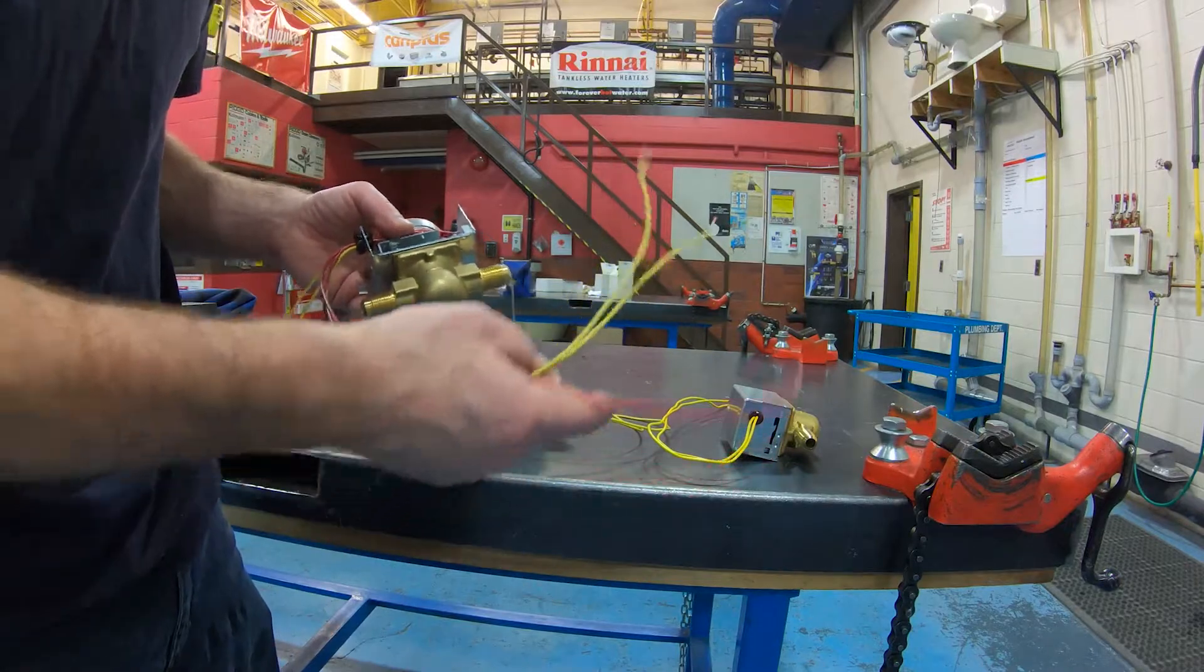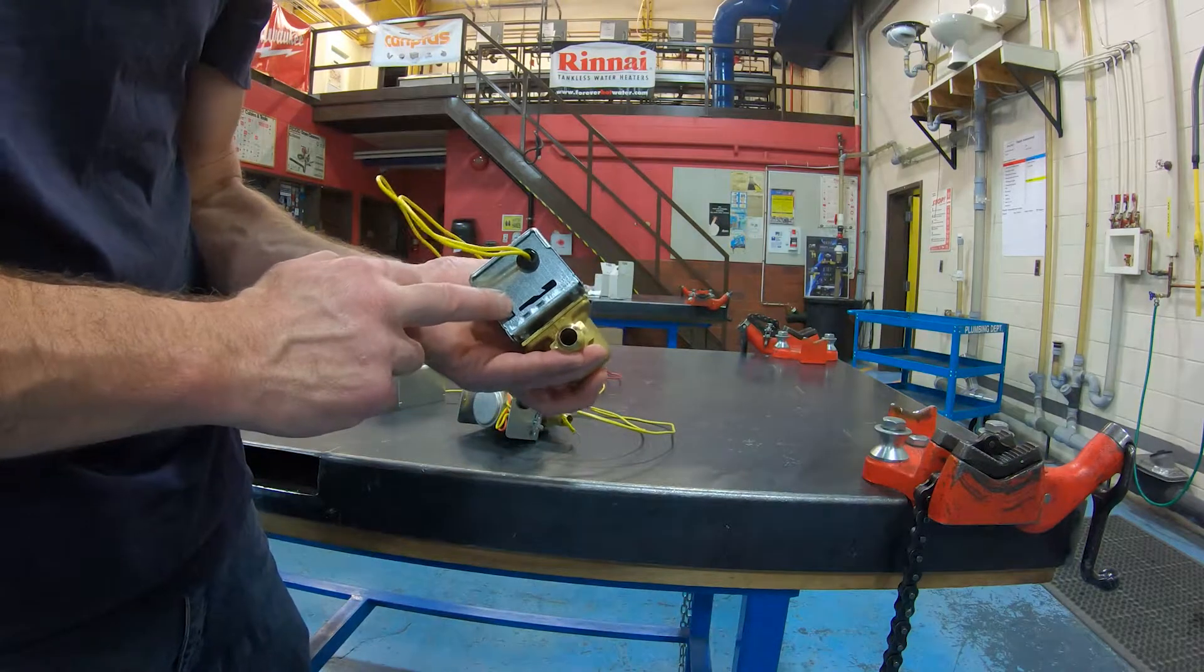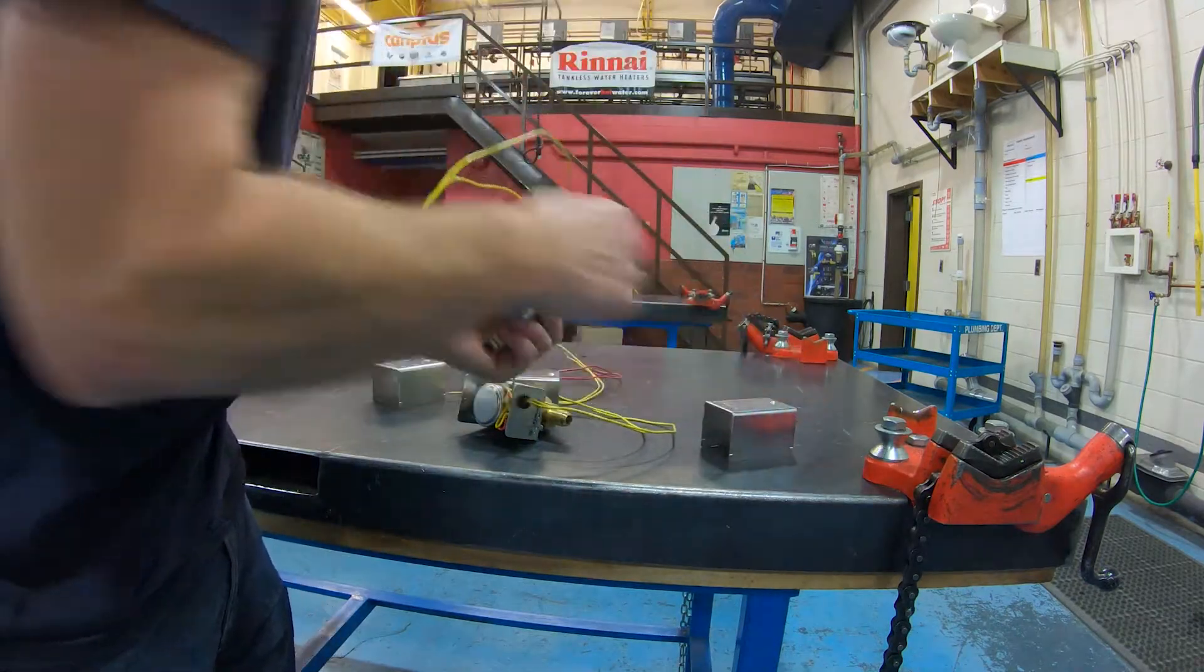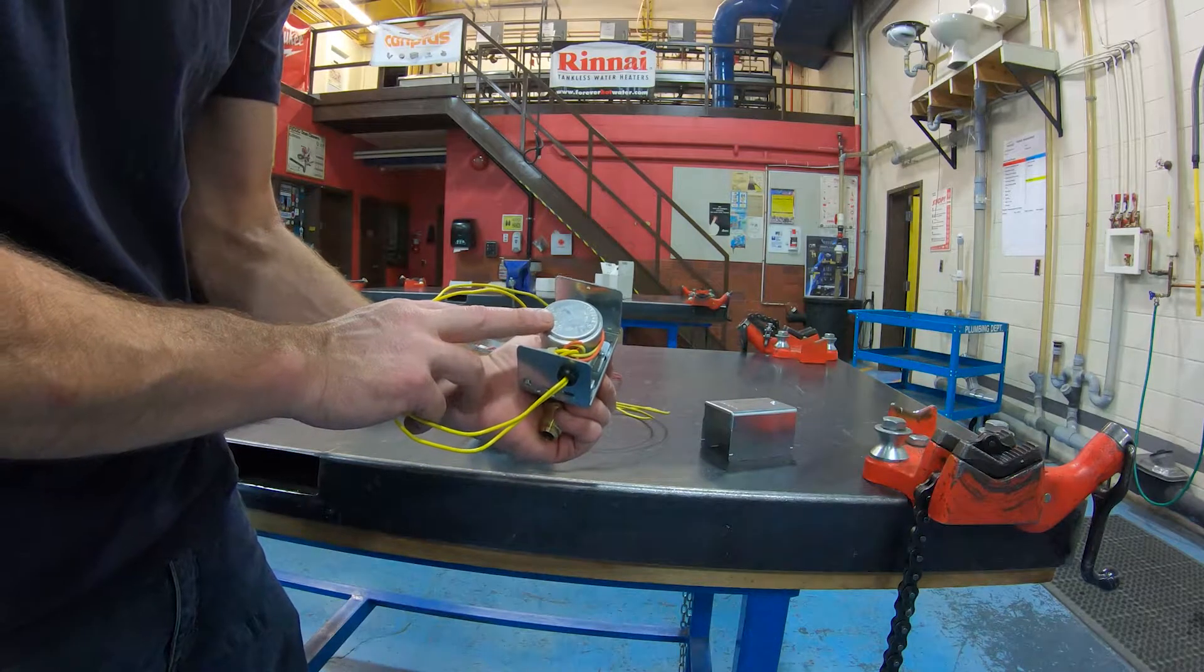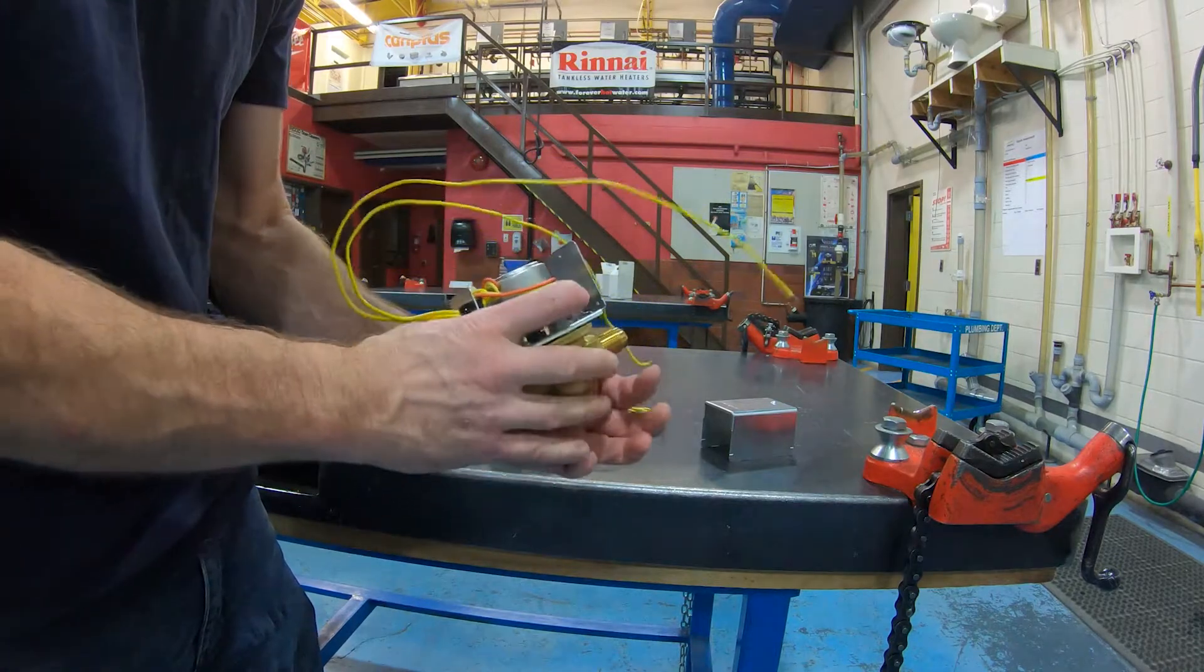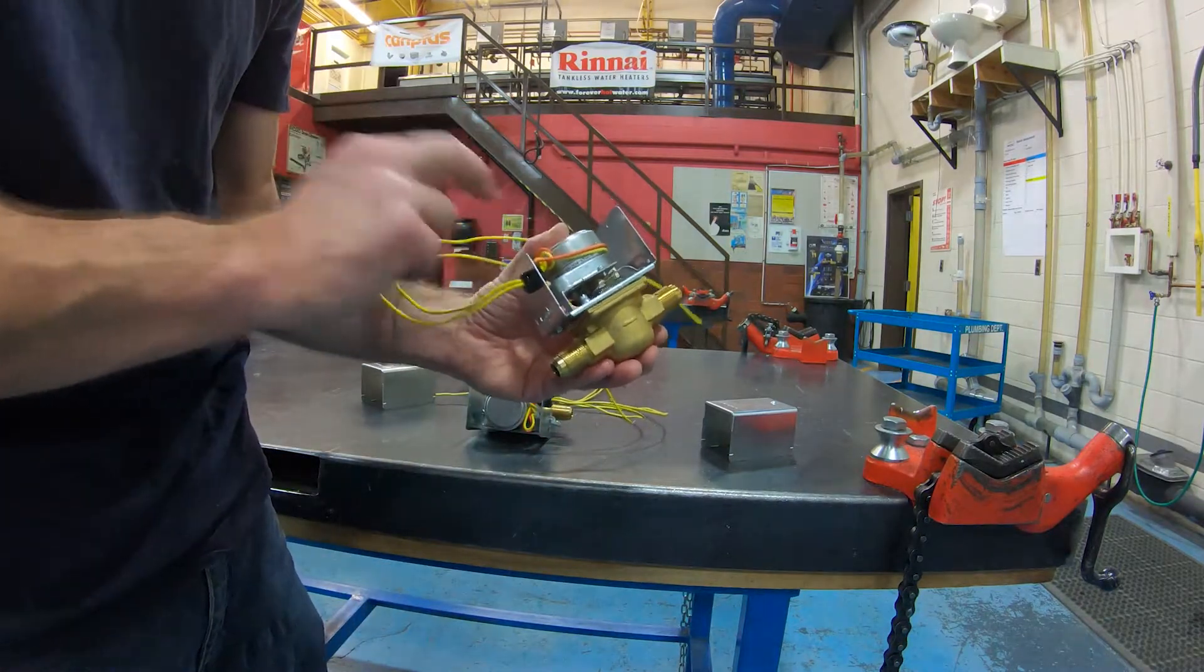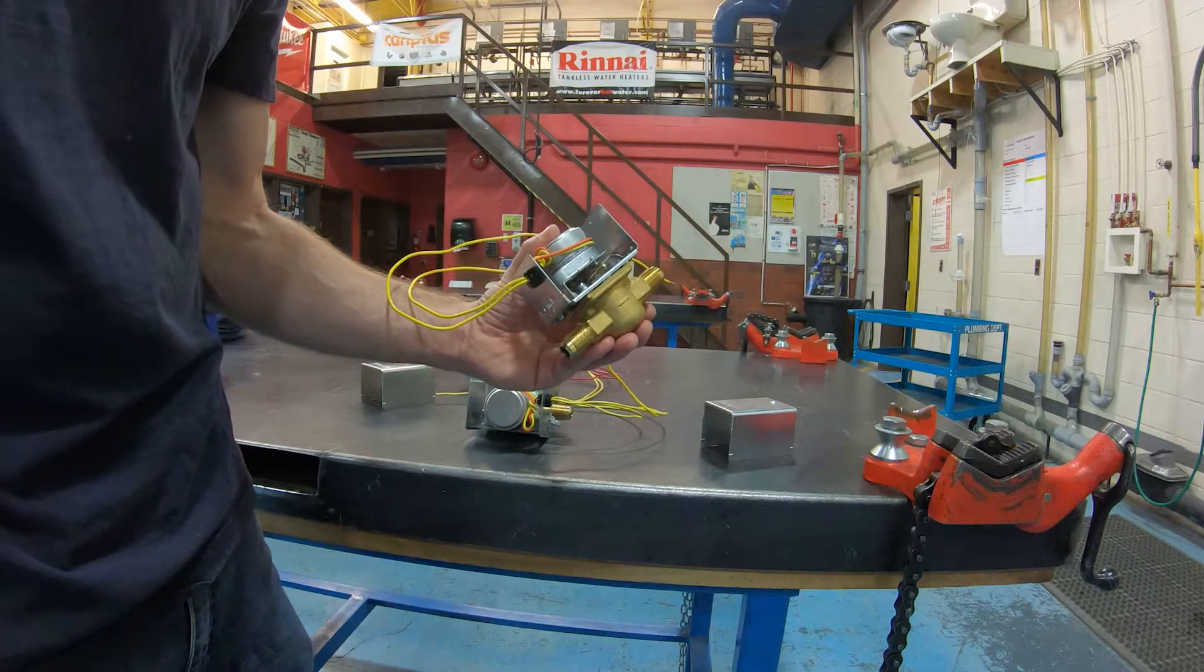Now the third type is a little bit weird. This type here has no manual tab. We call this a normally open zone valve. Still looks the same under the hood, we still have a zone valve motor, still a 24 volt actuator, still just two wires so there's no end switch on this. However, this particular type allows the water to flow through it until power is put onto the actuator. So no power means it keeps flowing. That's for safety purposes, we'll talk about that later.